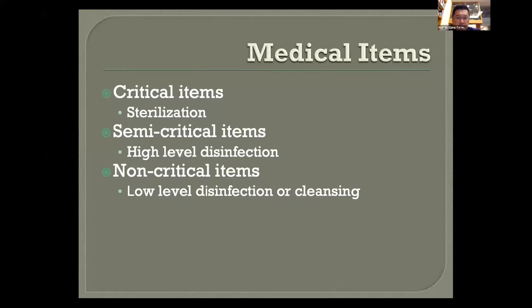So by definition, sterilization means you have to remove, kill, or deactivate all forms of life. In particular, we refer to microorganisms such as fungi, bacteria, spores, any unicellular eukaryotic organisms such as Plasmodium, and other biological agents such as prions. So we have different methods of sterilization. We all understand we have physical methods. We can use steam, dry heat, radiation, hydrogen peroxide plasma. We may also use chemical ways of sterilization, such as ethylene oxide gas or activated glutaraldehyde, or we may use peracetic acid.